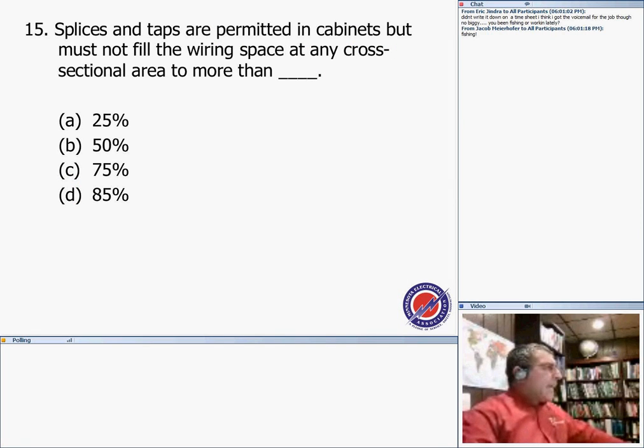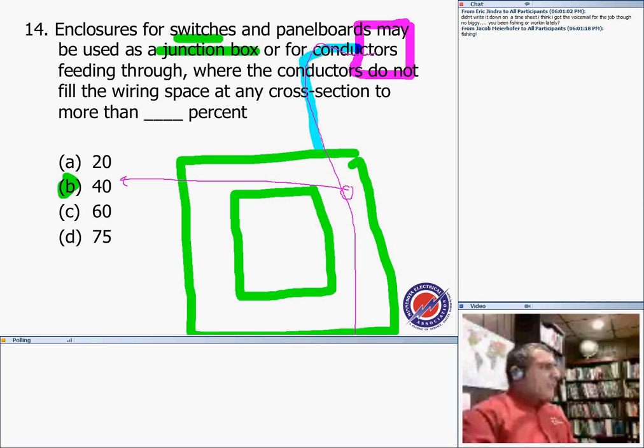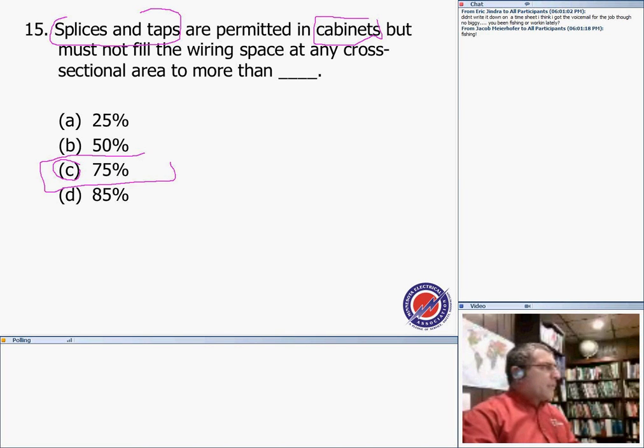Splices. Can I splice? No problem. Or taps are put in cabinets, switchgear, switchboards. As long as you don't fill more than, anybody remember? More than 75%. If you are to splice, so now I got into another issue. I'm going to splice right in here for whatever, bring it to the overcurrent device, then splice from here and go through this box, through this fixture to another fixture, right? So I splice as long as that splicing does not fill more than 75%. So we killed this horse.